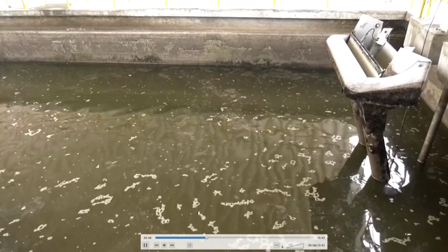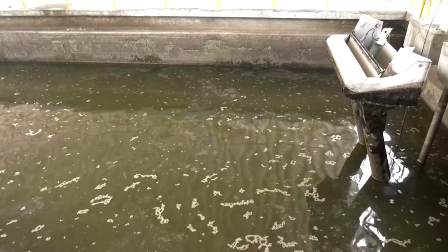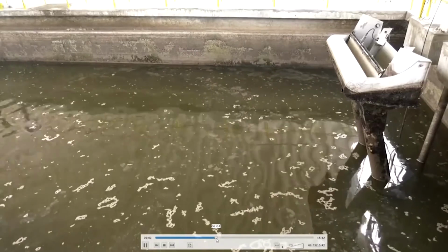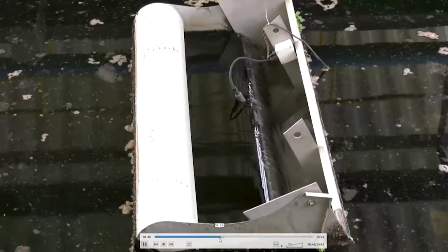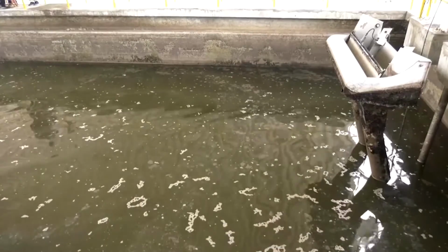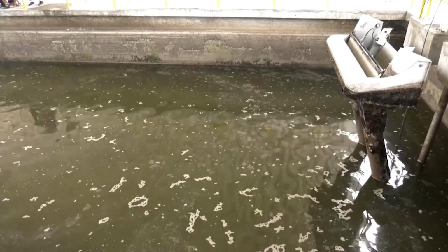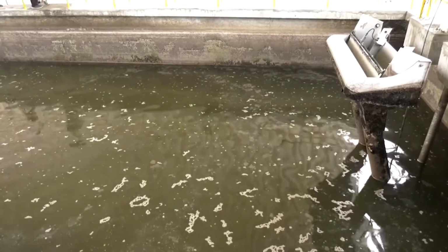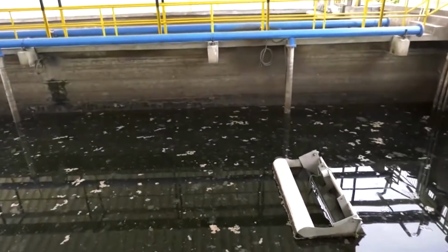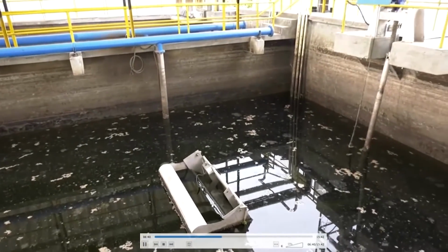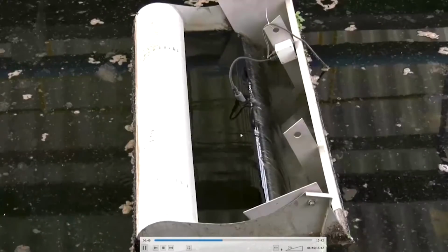Let's move ahead. So settling, again from the top, it doesn't look like much, but obviously when we just stopped aeration and the flocks were at the surface, you could see the difference acutely, and over time the microbes, or the sludge, are going to settle down. After we provided enough time for these microbes or the sludge to settle down, right? Again, type 1, maybe not type 1, type 2 settling probably initially, and then type 3 and 4. What are you going to have? You are going to have relatively clear water on the surface, and that water is being decanted, decantation. The water at the top is being removed, right? So that's what you have out here.